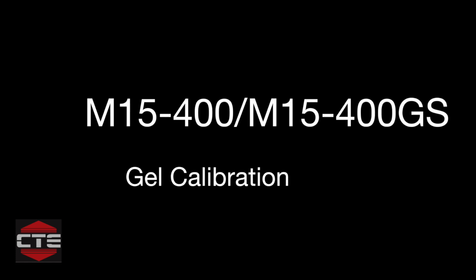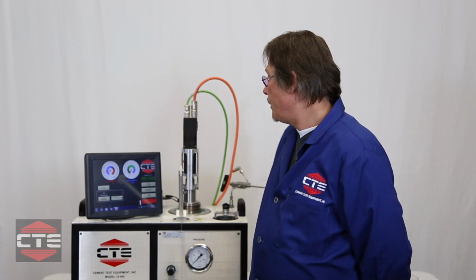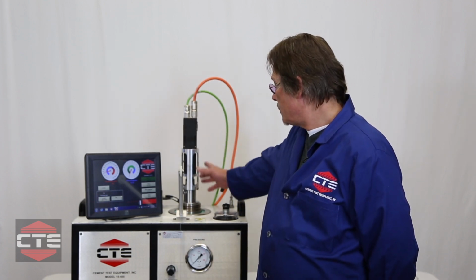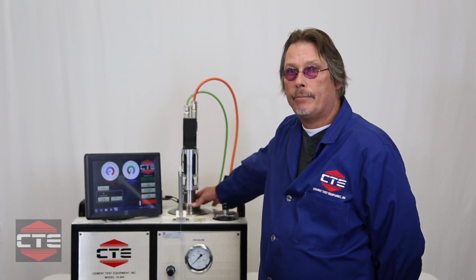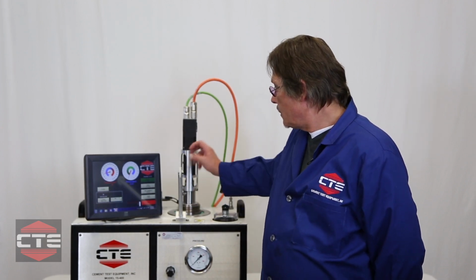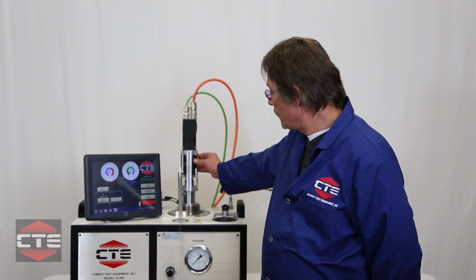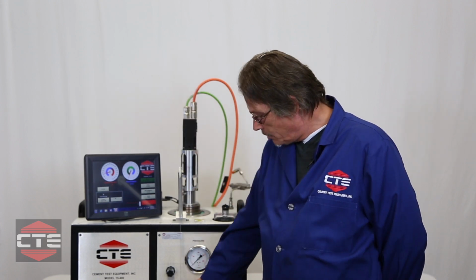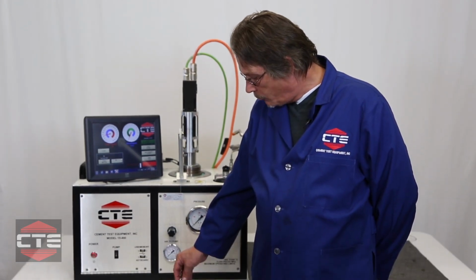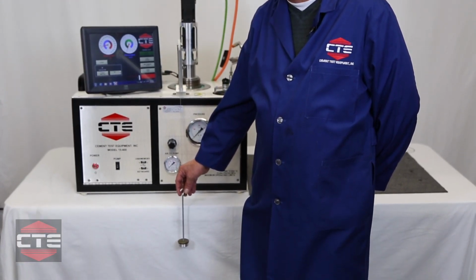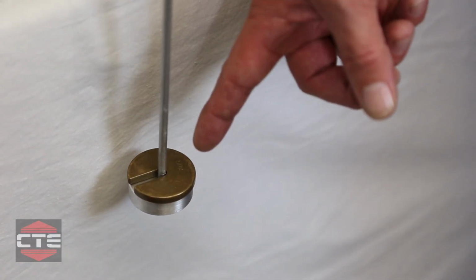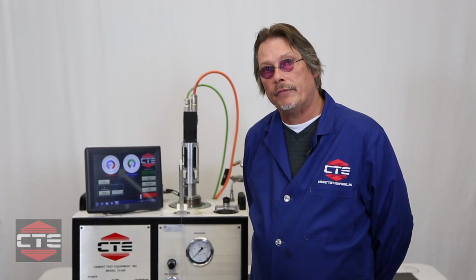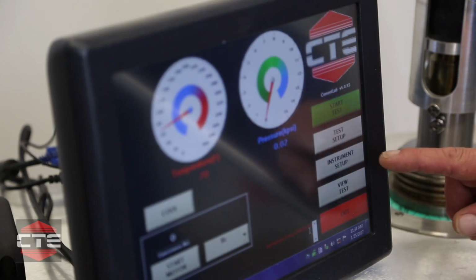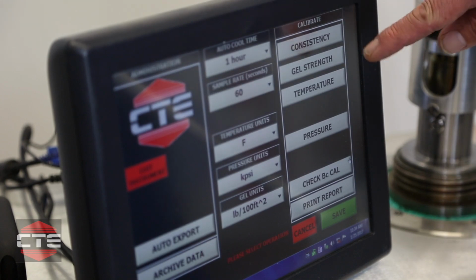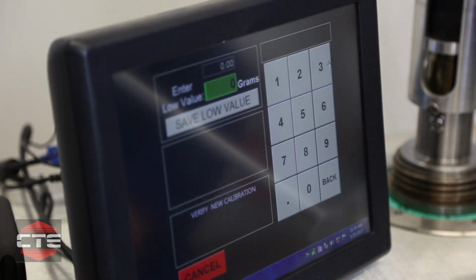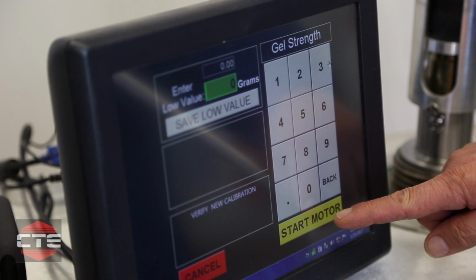So now we're ready to do our gel strength calibration. As you can see, I have the motor engaged. The slurry cup is dry, paddle only, head engaged, cable attached to the motor through screw on the calibration arm, and I have 50 grams weight holder plus 50 grams of weight for a total of 100 grams. If you do not have a gel strength option on your machine, please fast forward this video for consistency calibration. We're going to go into instrument setup. Our calibrate list here, we're calibrating gel strength. And we're going to start motor.